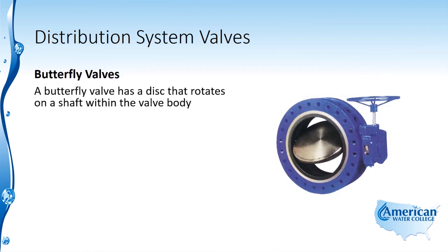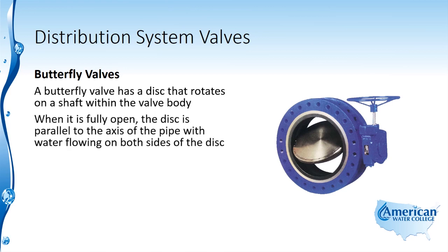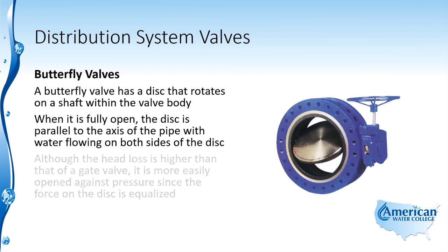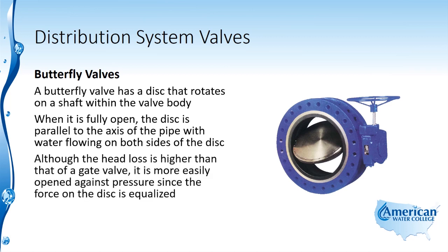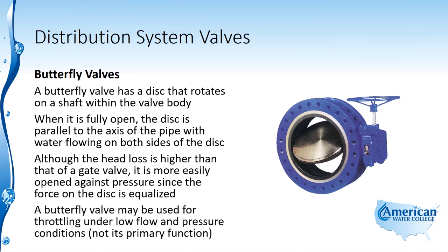A butterfly valve has a disc that rotates on a shaft within the valve body. When it is fully open, the disc is parallel to the axis of the pipe with water flowing on both sides of the disc. Although the head loss is higher than that of a gate valve, it is more easily opened against pressure since the force on the disc is equalized. A butterfly valve may be used for throttling under low flow and low pressure conditions, but this is not its primary function.